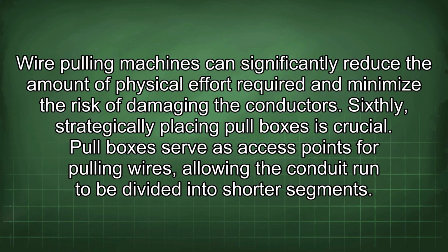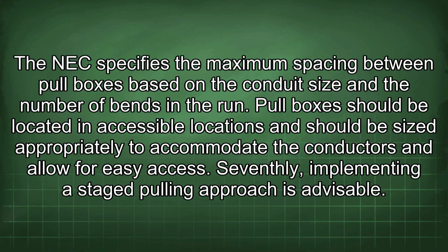Sixthly, strategically placing pull boxes is crucial. Pull boxes serve as access points for pulling wires, allowing the conduit run to be divided into shorter segments. The NEC specifies the maximum spacing between pull boxes based on the conduit size and the number of bends in the run. Pull boxes should be located in accessible locations and should be sized appropriately to accommodate the conductors and allow for easy access. Seventhly, implementing a staged pulling approach is advisable.